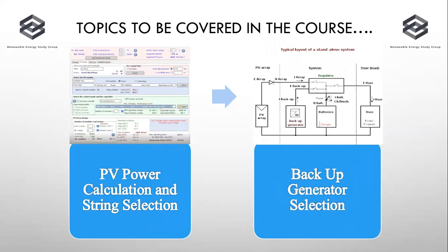The next point we're going to talk about is PV power calculation and string selection. Whenever we design any solar power plant, the key question is how to design the solar array — how many panels are required and how to make the series and parallel connections. In PVSyst software, by taking a company's solar panel and balancing the voltage and current using the relevant formulas, we can easily calculate the number of panels required and how to make the string and array connections.